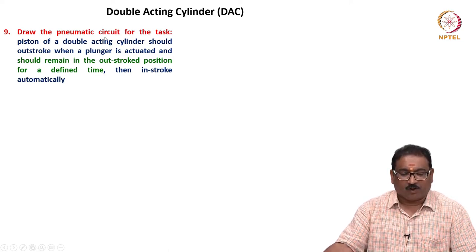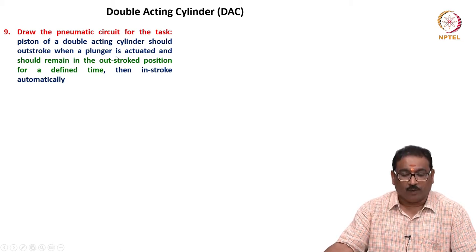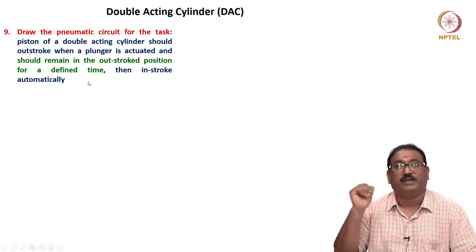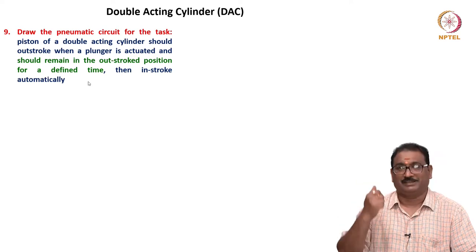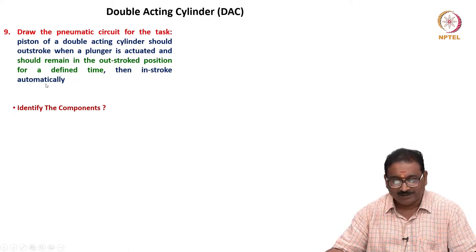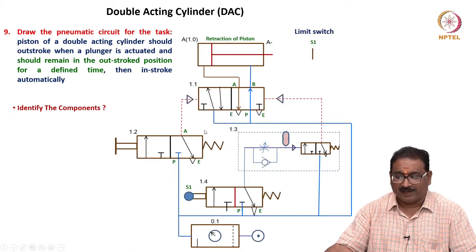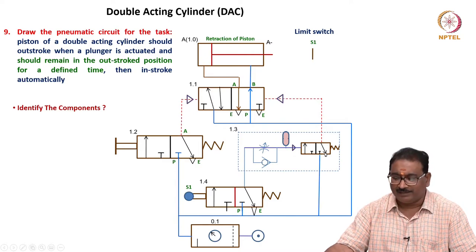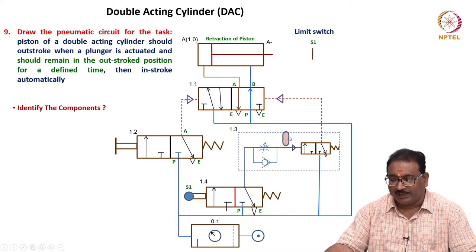Now we will see the ninth problem. Draw the pneumatic circuit for the task: the piston of a double-acting cylinder should outstroke when a plunger is actuated and should remain in the outstroke position for a defined time - 10 seconds, 20 seconds, 30 seconds - because loading and unloading operations may take place. Then in-stroke automatically after waiting for a certain period. The key component added here is a time delay valve. The time delay valve is a 3/2 DCV, with a throttle based on the time required to fill the accumulator.